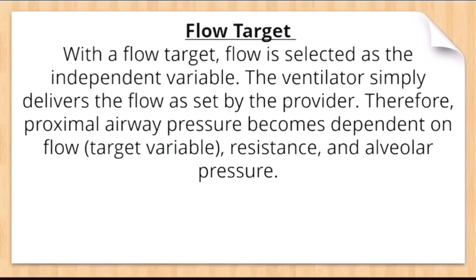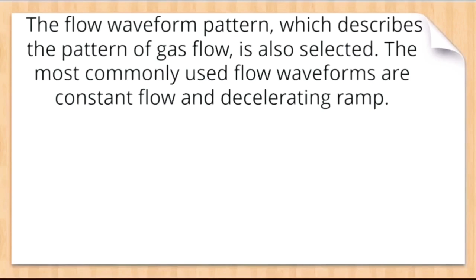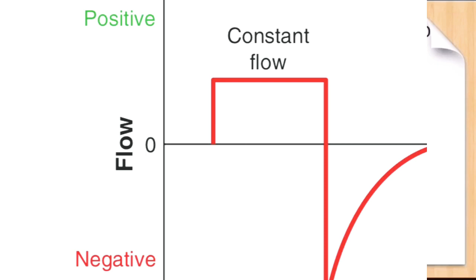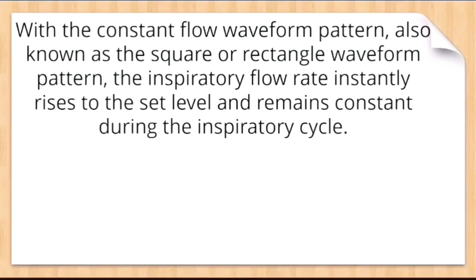Now, the flow waveform pattern, which describes the pattern of gas flow, is also selected. The most commonly used flow waveforms are constant flow and decelerating flow. Now, what is the difference between decelerating and the constant flow? You can see in this figure, with constant flow waveform pattern, also known as the square waveform pattern, the inspiratory flow rises instantly to the set level and remains constant during the inspiratory cycle. So you can see the figure, the relationship between the flow and the time. This is the constant flow waveform pattern, also known as the rectangular or square waveform pattern.